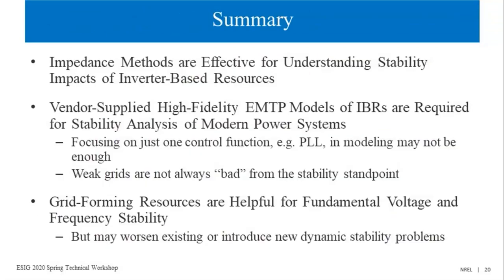So, concluding my presentation, impedance methods are becoming more and more attractive for understanding stability issues in inverter-based resources. As Fred mentioned, we need vendor-supplied high-fidelity models until we standardize controls of wind turbines and inverters to the point that we can really trust generic models. Till that point, we really need vendor-supplied models. And one counterintuitive finding is that weak grids are not always bad from the stability standpoint. I'm not saying that we have to have a weaker grid because they bring a lot of stability issues, but we can't blame weak grids for all the oscillations that we see in inverter-based resources. So we have to be mindful about that.